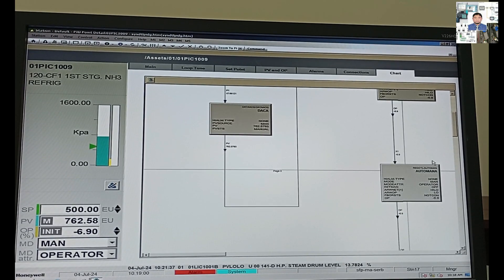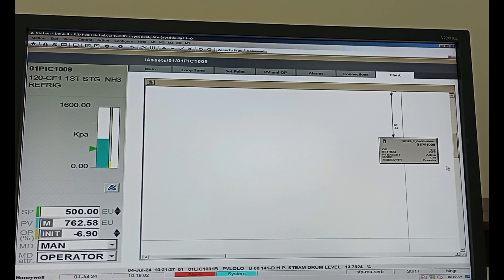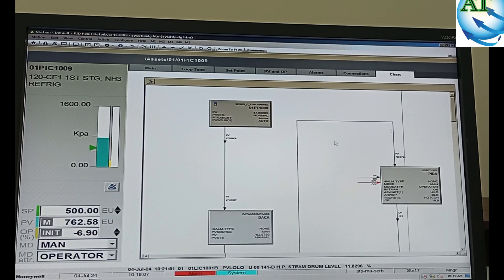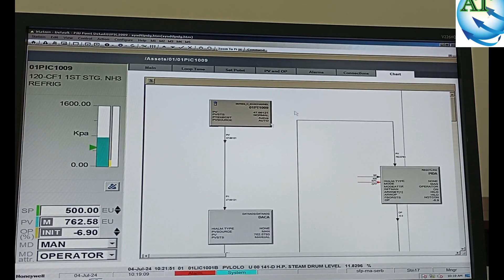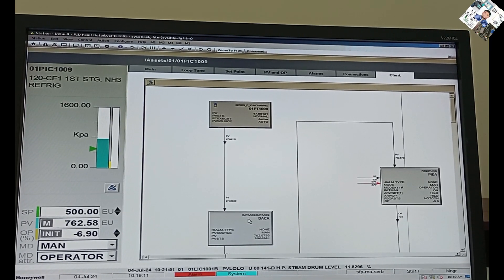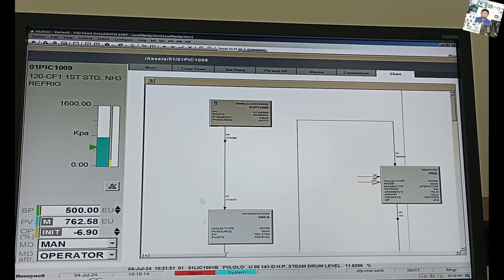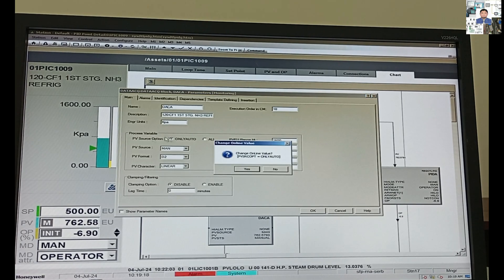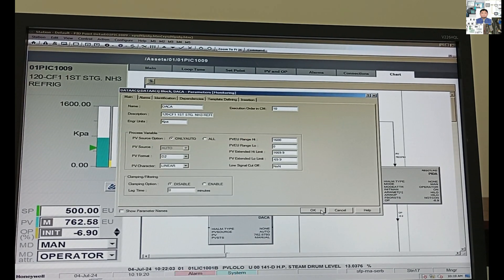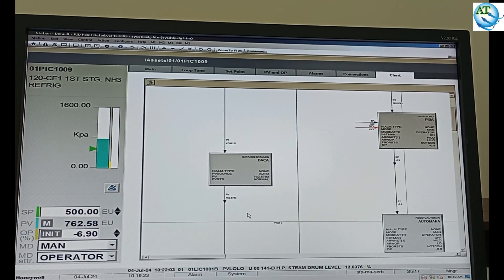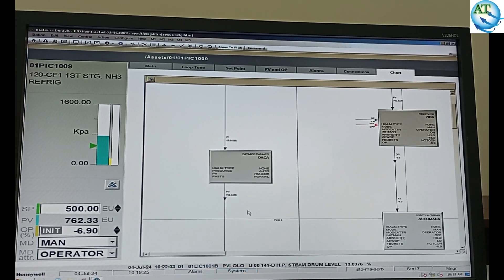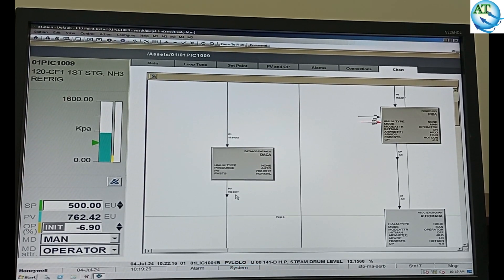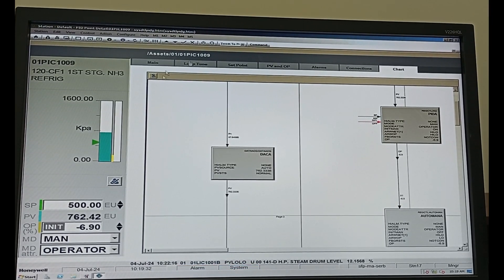I have suggested that you must force the analog input before maintaining any transmitter. If you make any mistake — without forcing — and change the field instrument or transmitter, then the process will be hampered and sometimes the process can be stopped or the plant can trip. After maintenance work, you only go to the DACA block and press only-auto mode — then the live value will come to the logic and the whole value will return to normal.